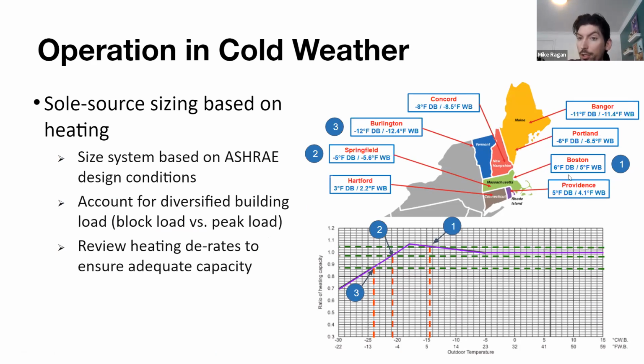At Boston design temperature, which is 6 degrees Fahrenheit dry bulb, we're going to be looking at this red line right here that's running to the bottom. So that's going to be at the 6 degree line that runs up. And what capacity are we getting at 6 degrees? We're getting over 100% of our capacity. And the reason we're getting that is because of the flash injection technology that we previously mentioned. That's going to give you more robust heating performance in cold temperatures.